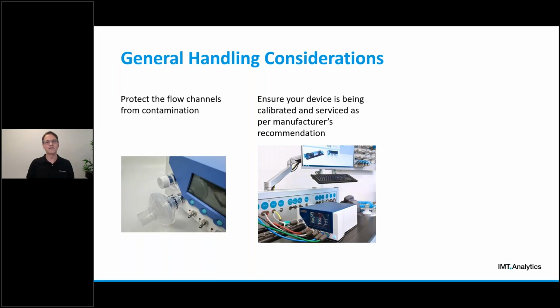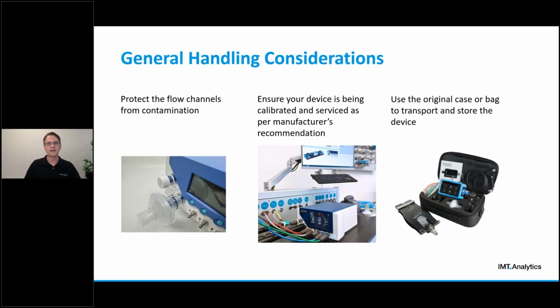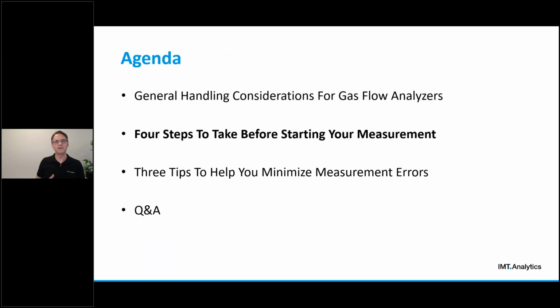Secondly, please ensure that your device is being calibrated and serviced as per the manufacturer's recommendation. Most gas flow analyzers are on a 1-year calibration and maintenance schedule, and it's of highest importance that the accuracy of your measurements is being verified frequently. And lastly, make sure that you use the original case or bag to transport and store the device in order to protect it properly. These are high precision measurement instruments that must be handled with care. Okay, so that was it about the general handling considerations. Now let's dive into the 4 steps you should always take before you even start your measurements.